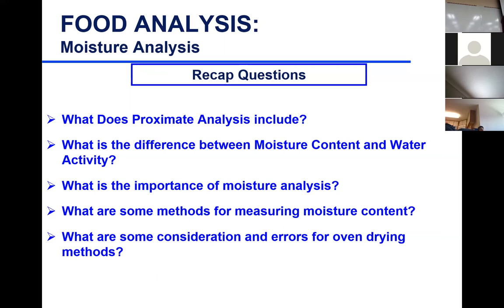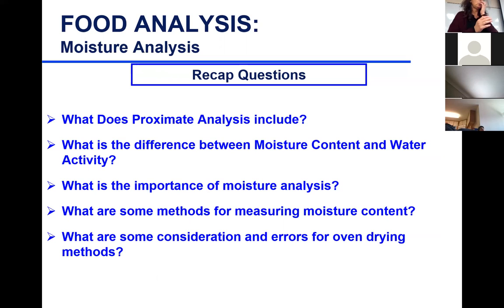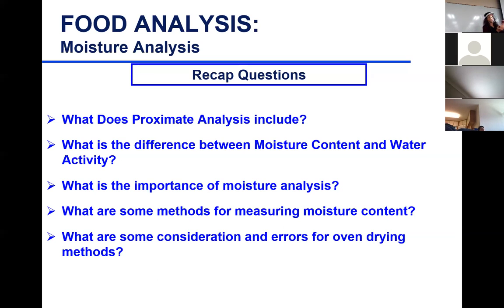What is the difference between moisture content and water activity? Moisture content is the total amount of water that is not chemically bonded to different components, whereas water activity is actually the ratio of the vapor pressure of water from the headspace over the sample to the pressure of pure water — so it's the relative measure.